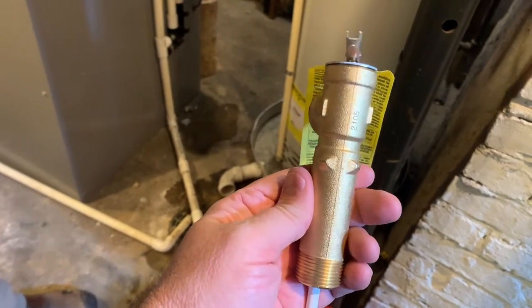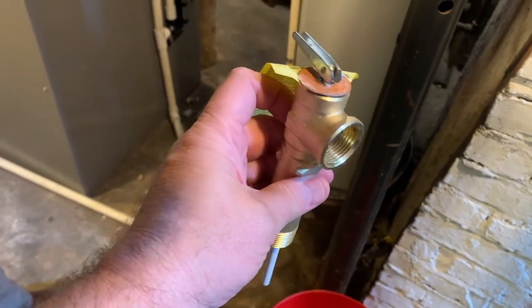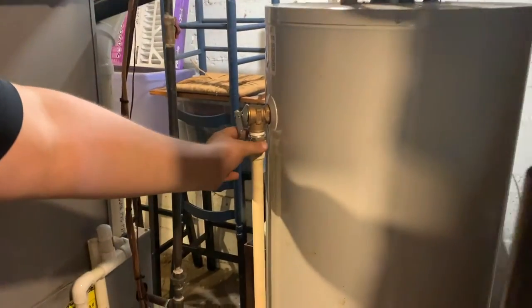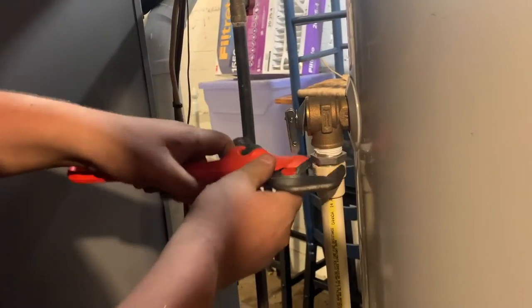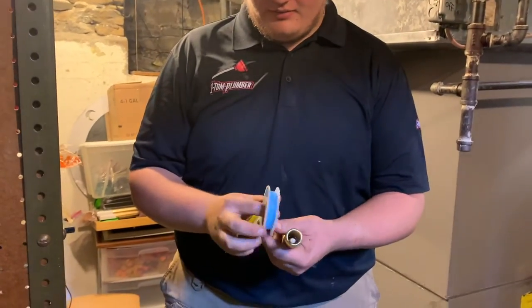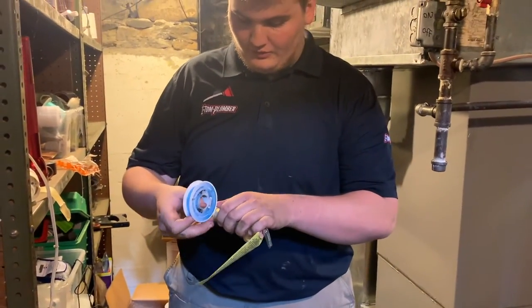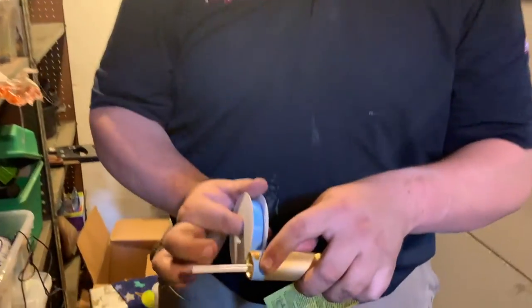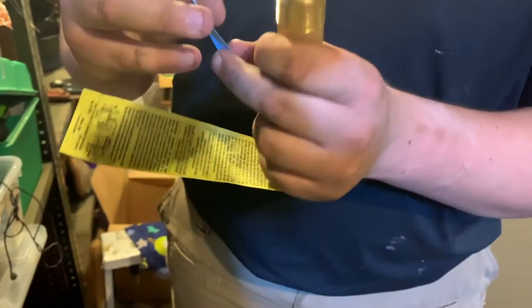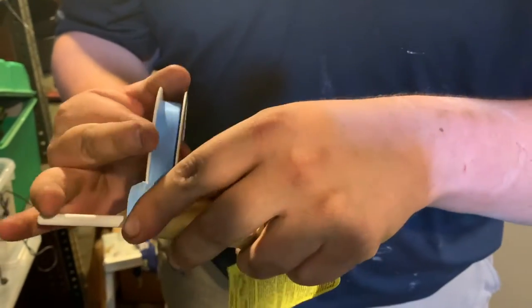This is the new valve we're going to replace it with. This is the main part — there's a spring inside, there's a gasket inside, the whole bit. After you've got everything drained, what you'll want to do is unthread this piece. We've got our new T&P valve, and in order for this to seal properly inside of the tank, you're going to need to apply some kind of thread sealant. Today I'm using Teflon tape, and I'm going to put some liquid Teflon tape on it too, just so we know for sure that there will not be any leaks.